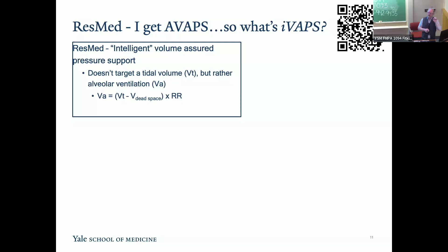And that's the ResMed diagram of just how intelligent they are. And then it's targeting the minute ventilation for alveolar ventilation. And so this diagram here on the left is the typical: target patient minute ventilation is decreasing, ramp up the pressure. Oh, the target alveolar ventilation is too high, ramp down the pressure. So you input in the device a target alveolar ventilation and a target breath rate.